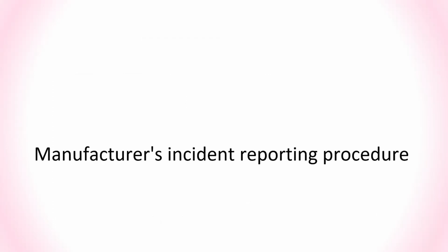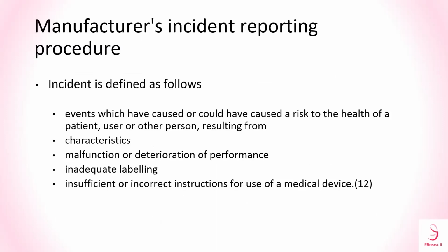Manufacturer's Incident Reporting Procedure. Incident is defined as follows: events which have caused or could have caused a risk to the health of a patient, user, or other person, resulting from characteristics: malfunction or deterioration of performance, inadequate labeling, insufficient or incorrect instructions for use of a medical device.